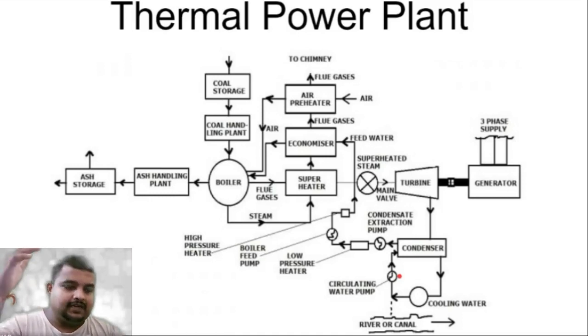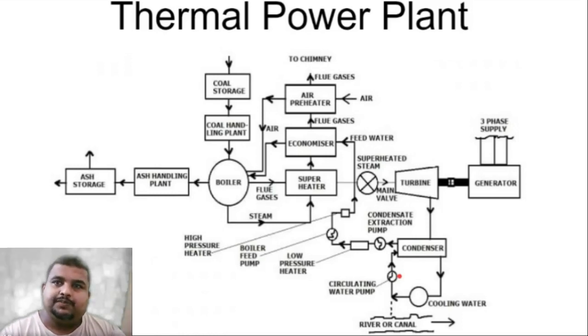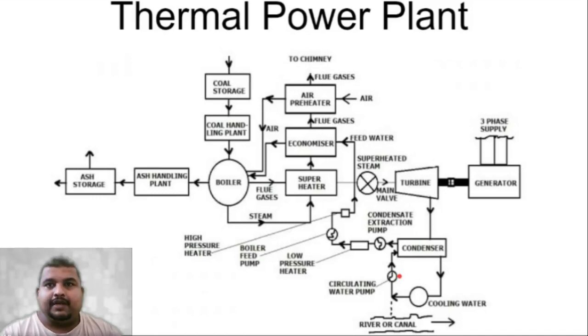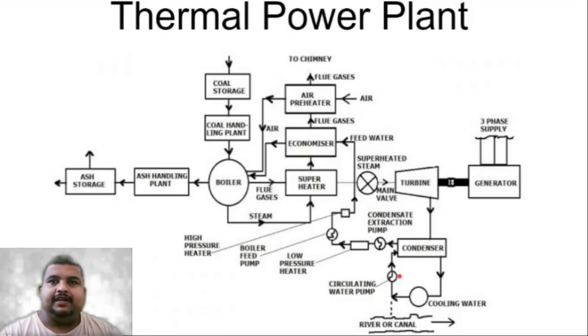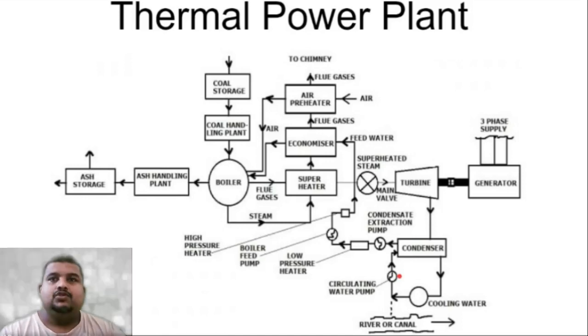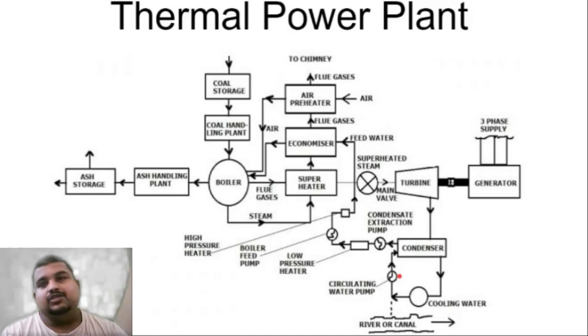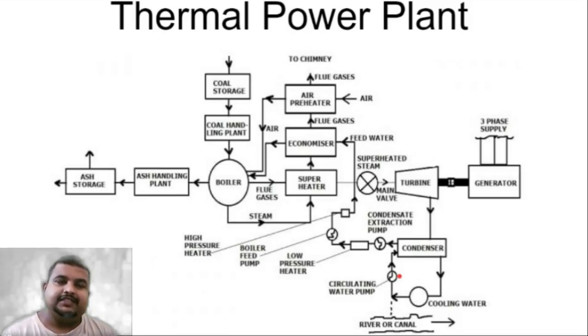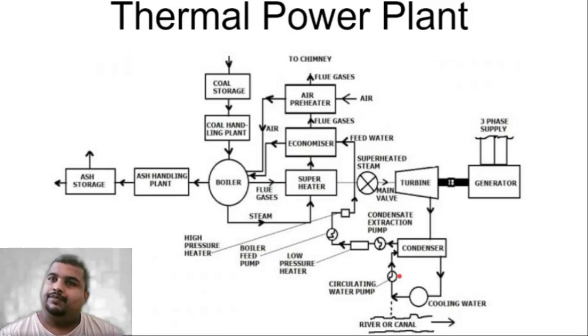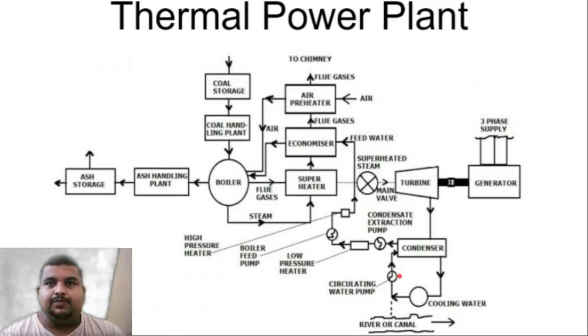There is a condensate extraction pump (CEP). The condensate that has come here is given a little heat — this is done using low pressure steam in the low pressure heater. This heater is also called a heat exchanger, which extracts heat from one fluid and transfers it. After this, the heated water is given to the BFP — the boiler feed pump.